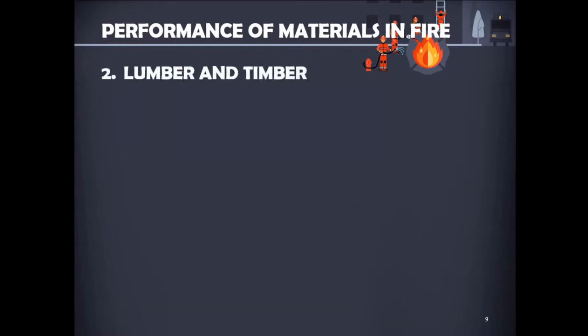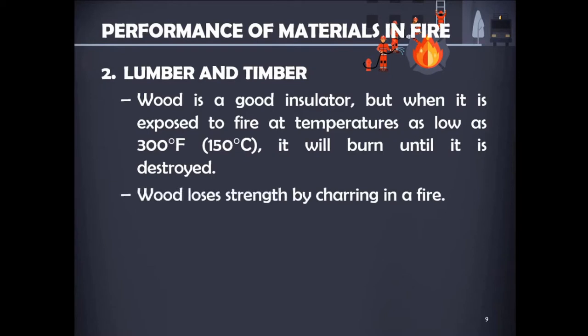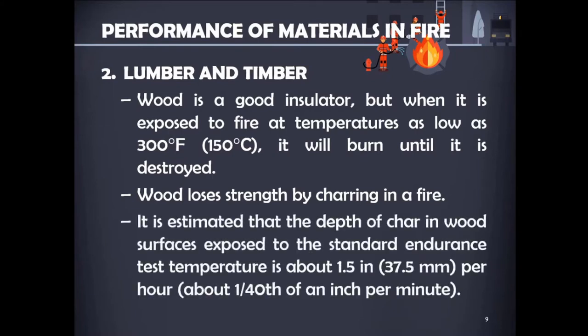The second material is lumber and timber. Wood is a good insulator, but when exposed to fire at temperatures as low as 300°F (150°C), it will burn until it is destroyed. Wood loses strength by charring in a fire. The penetration of surface charring is fairly consistent with time — estimated at about 1.5 inches or 37.5 mm per hour, or about 1/40 of an inch per minute.